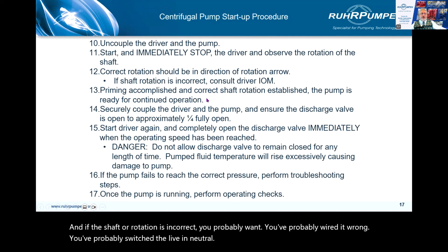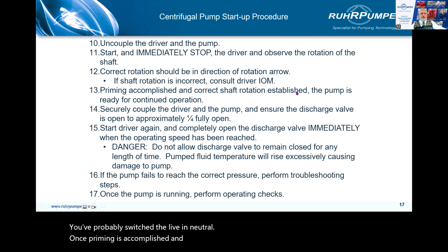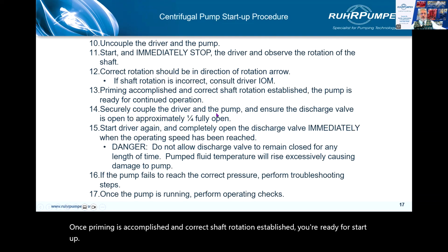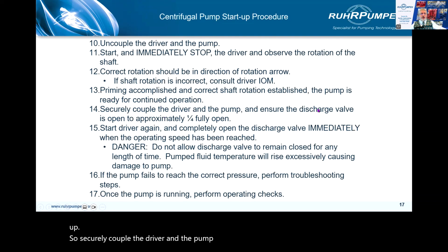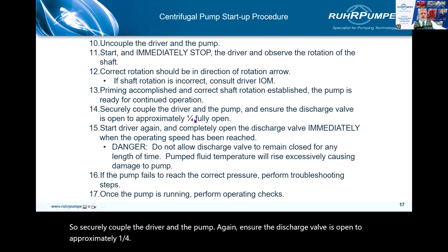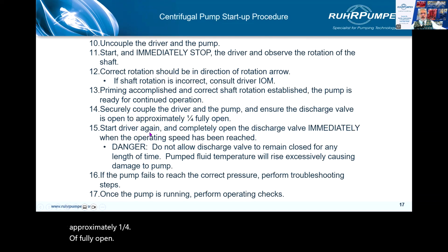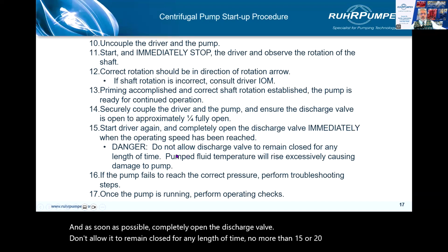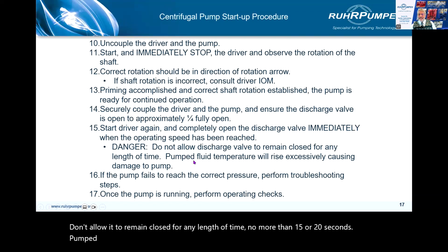Once priming is accomplished and correct shaft rotation established, you're ready for startup. So securely couple the driver and the pump again. Ensure the discharge valve is open to approximately a quarter of fully open. Start the driver again, and as soon as possible, completely open the discharge valve. Don't allow it to remain closed for any length of time, no more than 15 or 20 seconds. Pumped fluid temperature will rise excessively otherwise, causing damage to the pump.